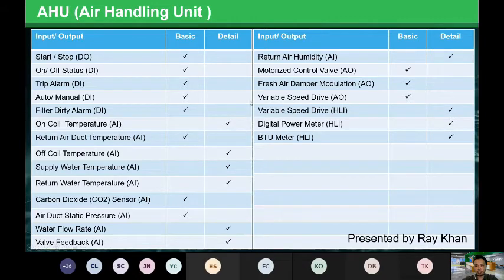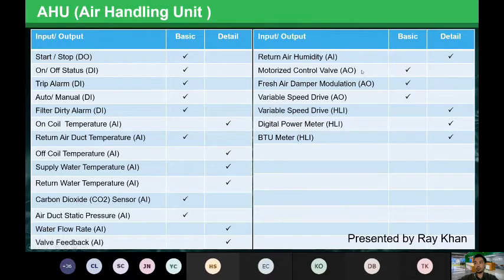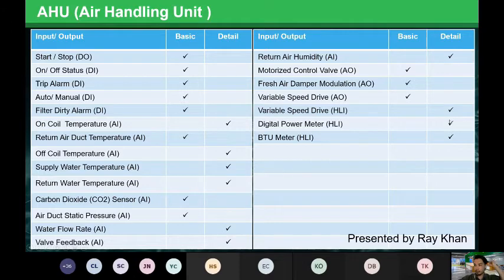From this table you can see some points are good-to-have details — for example, on-coil temperature, off-coil temperature, supply water temperature, and return water temperature are all detail points. Water flow rate and valve feedback are similarly detailed. Return air humidity is also a detail point. Analog outputs include: control valve, damper modulation, and variable speed drives. Detail points also include variable speed drive, power meters, and BTU meters.